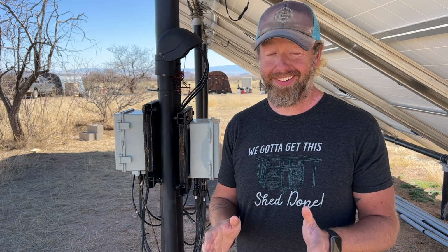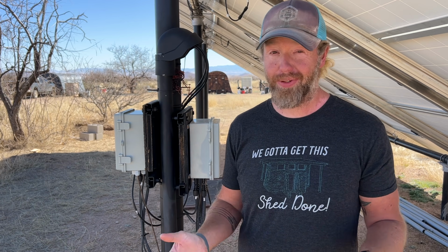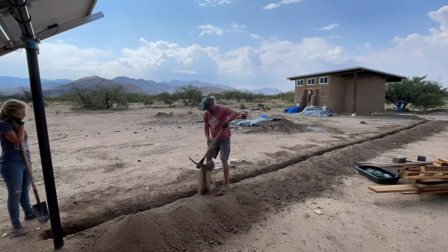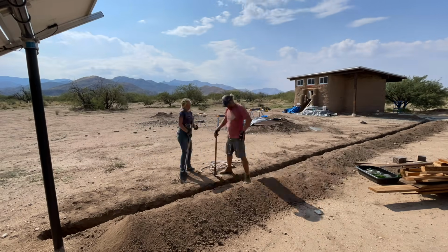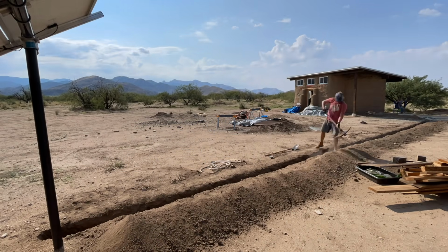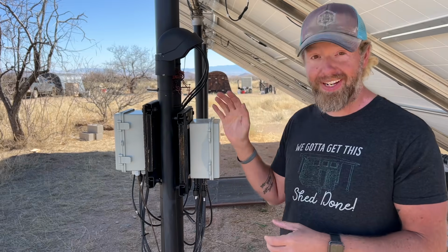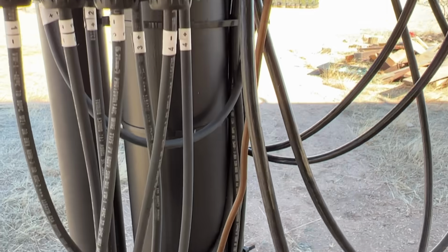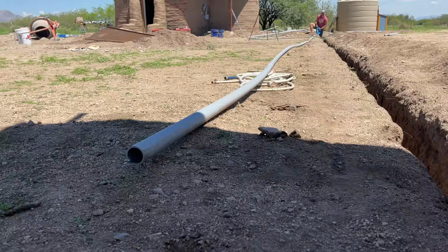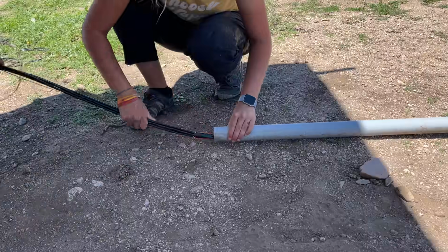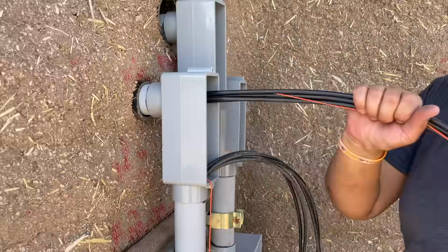Next up is trenching. Now obviously everyone's trenching situation is going to be very different. Like we mentioned, we had to run a little over 100 feet from this array to the solar shed. So what we did is we took the positive and negative wire coming out of each of these, we ran it up through a service entrance, goes down into the ground, all the way over, and then through some LB connections on the outside of the solar shed.